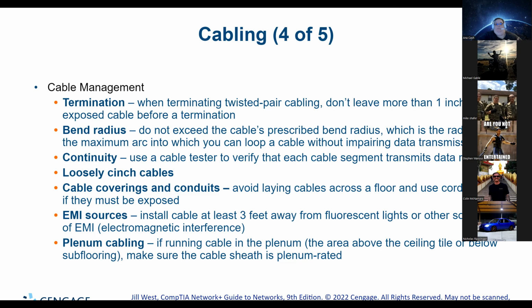And then there is plenum cabling. If running cable in the plenum, that's the area above the ceiling tile or below the subflooring, make sure the cable sheath is plenum rated. That's what we were talking about: a lot of the time when they do cable running in buildings, it's above the drop ceiling, or if they have a raised floor, it's below the subflooring too.